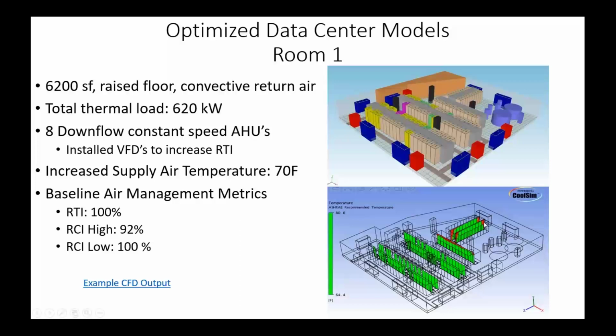Now you see a little bit of tearing right there on the edge. To do this, we use the containment. So there's your containment sitting there. I just blocked it in so you can see that I put a box effectively around the cold side. The result is that it's in pretty good shape. I still have that problem over here, a little bit of falling out, but it's in the high 90s. The other thing we did here is raise supply air temp to 70 degrees. So we moved supply air temp up 10 degrees, which is going to make everything more efficient. Same exact data center, now we've just used air management.